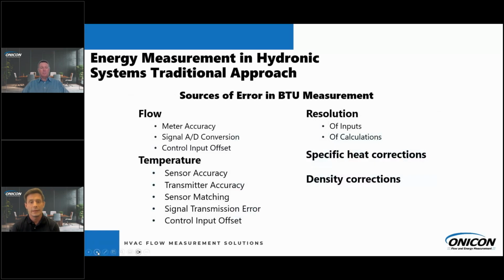So let's look at all the errors that we're taking into consideration, and this is why we believe you should put it on us to ensure you're getting an accurate BTU calculation. As I mentioned before, it's extremely important to have a temp sensor that's matched, paired, and bath calibrated per its application. And that sensor accuracy is as important as the flow meter accuracy. There are all these other factors in computing, signal processing on the end, outputs, and the calculation itself that contribute to that error.